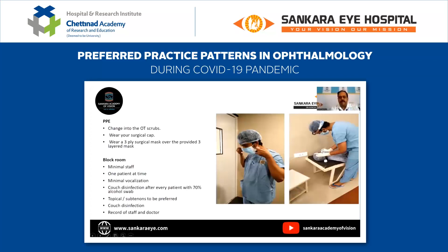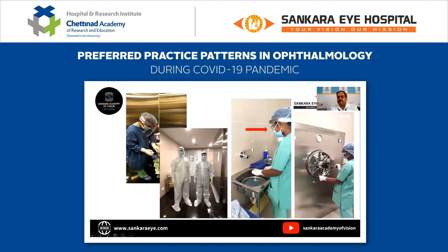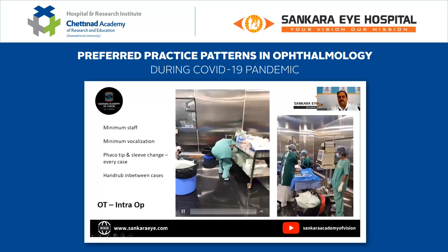The staff who are posted in the autoclave or the CSSD should wear a face shield because whenever they're washing the instruments, there is an aerosolization that is possible. Again, they're educated to remove it when they're handling the autoclave so that the heat from the autoclave does not affect it. Most of these shields are made of polycarbonate, but some of them are made from recycled plastics. So we are not very sure of the quality. So it is better that they are advised to remove it when they're removing the pins from the autoclave. Again, we encourage minimum staff. Whatever additional consumables are required between cases are kept outside the operation theatre so that there is no cross-contamination. So minimal manpower, and trolleys like this that we used to keep earlier should no longer be kept in the OT because again you want to reduce any possible cross-contamination.